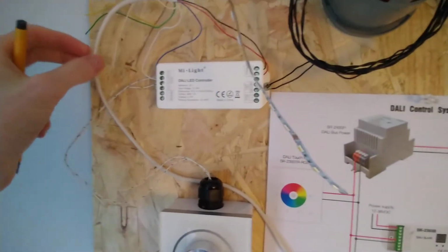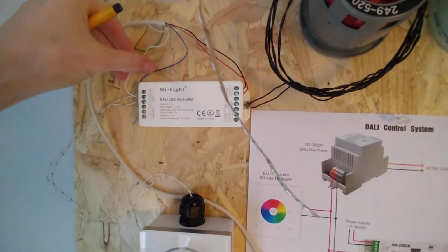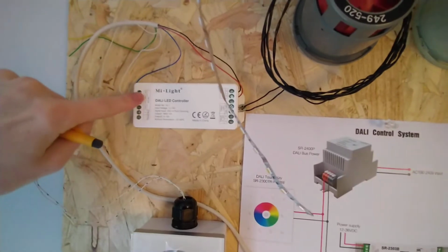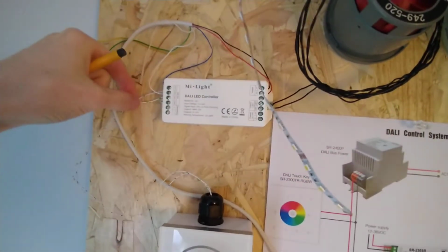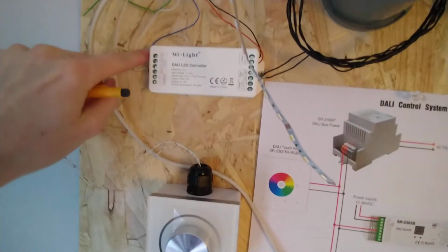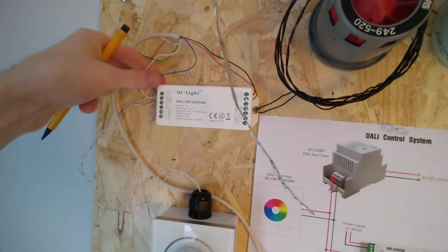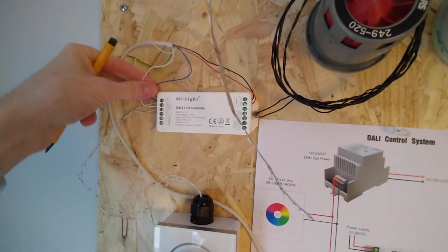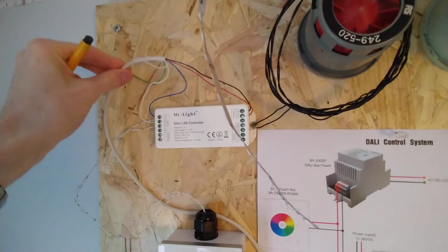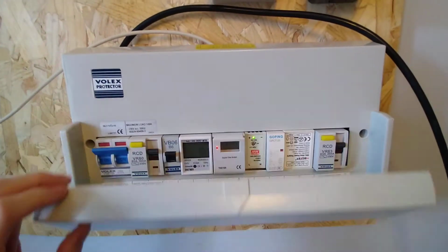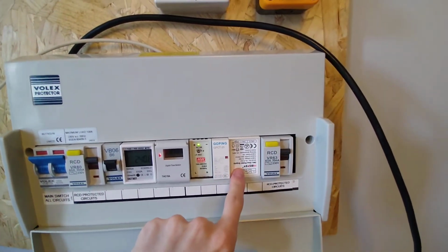So I've got a piece of cable here. These 2 wires are my bus power supply. That's going into this receiving device, and paralleled off that is my sending device. So there's my bus power. That's the blue and white on this cable here. That's the DALI bus power. So that runs down here. That runs into my DIN rail enclosure, and I've got a DALI power supply.